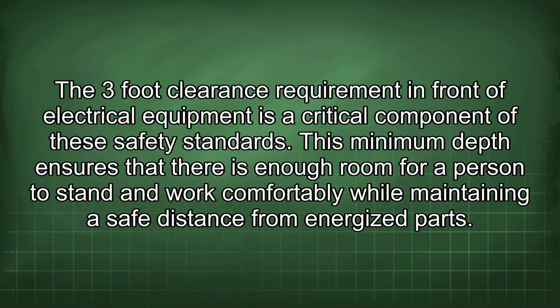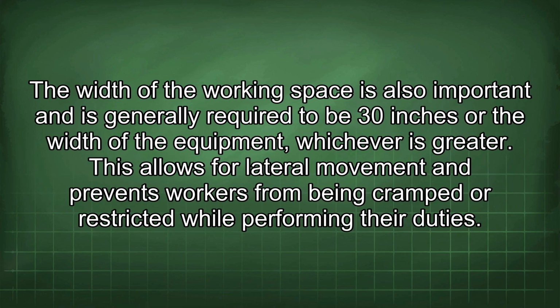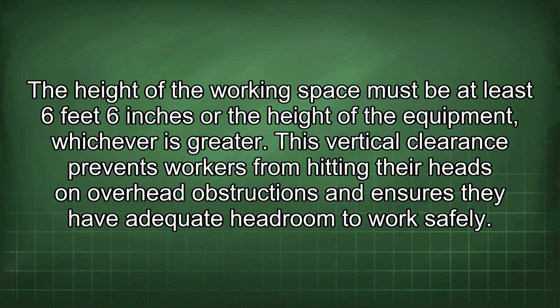The 3-foot clearance requirement in front of electrical equipment is a critical component of these safety standards. This minimum depth ensures that there is enough room for a person to stand and work comfortably while maintaining a safe distance from energized parts. The width of the working space is also important and is generally required to be 30 inches or the width of the equipment, whichever is greater. This allows for lateral movement and prevents workers from being cramped or restricted while performing their duties. The height of the working space must be at least 6 feet 6 inches or the height of the equipment, whichever is greater. This vertical clearance prevents workers from hitting their heads on overhead obstructions and ensures they have adequate headroom to work safely.